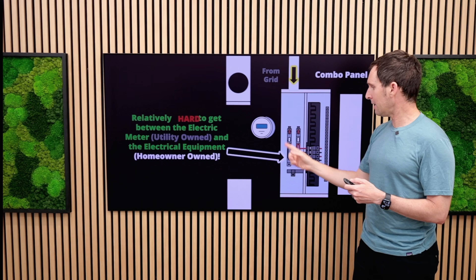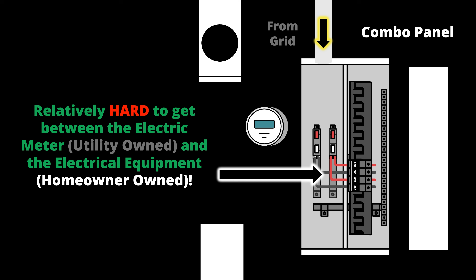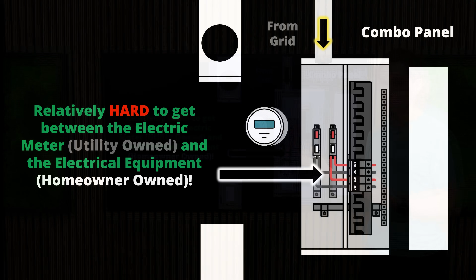Let's take another look at the combination panel. If we look at it, we find that the space between the meter socket and the bus bar, which the breakers land on - the homeowner side of the equipment - is actually very hard to get to. This is part of a UL, Underwriter's Laboratory, full specification and engineered product, which you really can't field adapt. You can't take this apart in the field easily and make new connections between the meter and the electrical equipment.